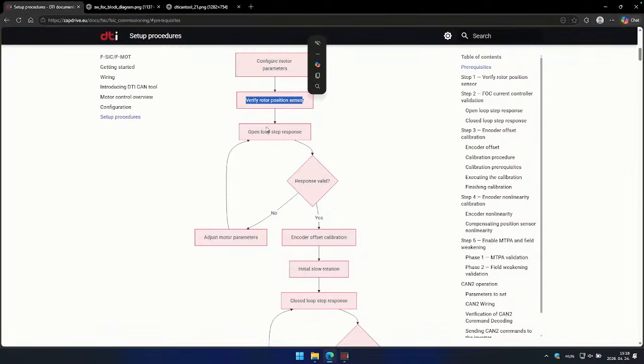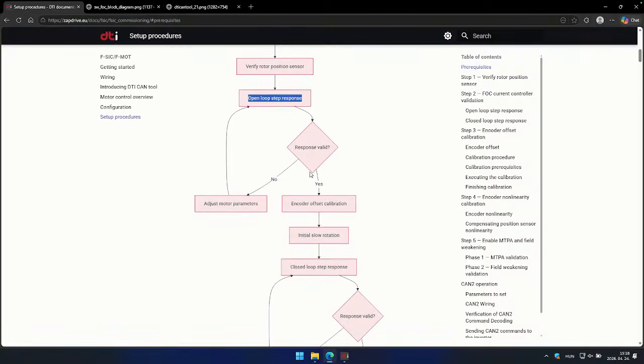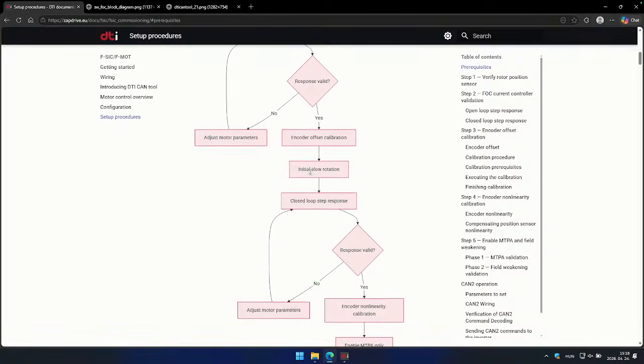First, verify the rotor position sensor operates correctly without controlling the motor, just statically. Then we do open loop step responses, analyze the response, and adjust the motor parameters if necessary, looping until you get a validated current controller.